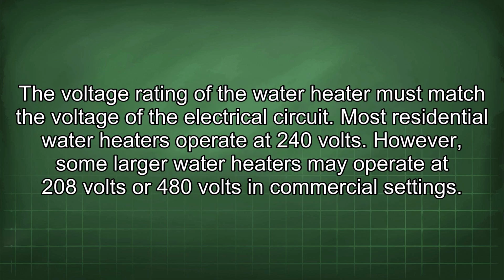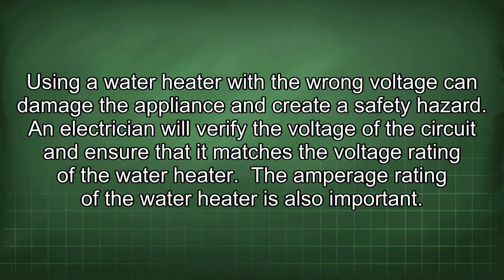The voltage rating of the water heater must match the voltage of the electrical circuit. Most residential water heaters operate at 240 volts. However, some larger water heaters may operate at 208 volts or 480 volts in commercial settings. Using a water heater with the wrong voltage can damage the appliance and create a safety hazard. An electrician will verify the voltage of the circuit and ensure that it matches the voltage rating of the water heater. The amperage rating of the water heater is also important.